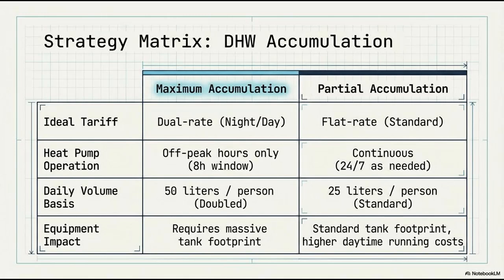That's a perfect analogy. You're hitting on the classic tension between capital expenditure, or CapEx, and operational expenditure, OpEx. CapEx versus OpEx. Right. So the warehouse strategy, maximum accumulation, requires significant upfront CapEx. I mean, a tank large enough to hold double the daily water supply for an entire family takes up serious physical real estate in a utility room. Yeah, it's huge. It's heavy, it requires reinforced flooring, and it's just expensive to purchase. But the corner store strategy saves you that upfront CapEx and physical space, but it locks you into a higher OpEx. You're paying daytime peak energy rates for the lifetime of the system.